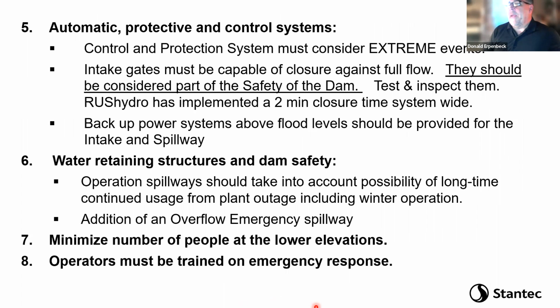The other thing that became clear is that once they lost power, the control and protection system couldn't do anything about it. They really hadn't considered extreme events in the design of the system and the protection. Not only could the turbines themselves not even shut off, they couldn't close the emergency devices. They couldn't even handle the normal shutdown sequences, they lost normal controls, not to mention being unable to close the intake gates.